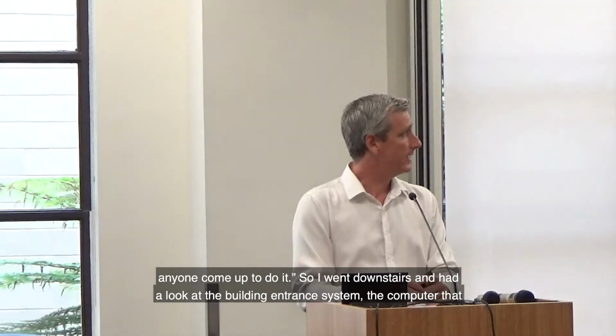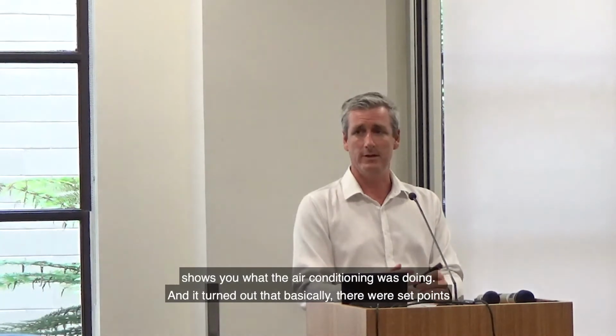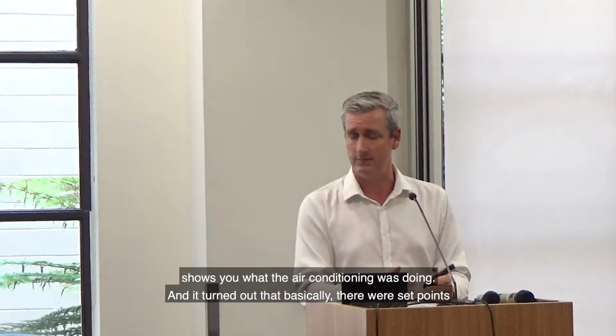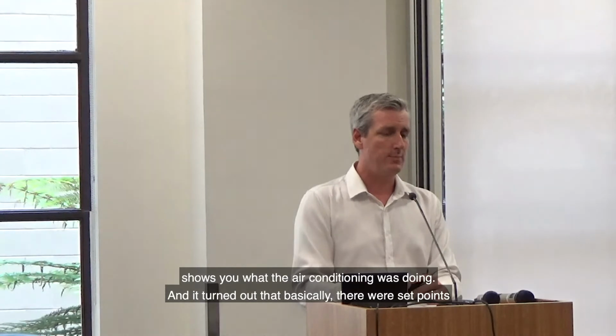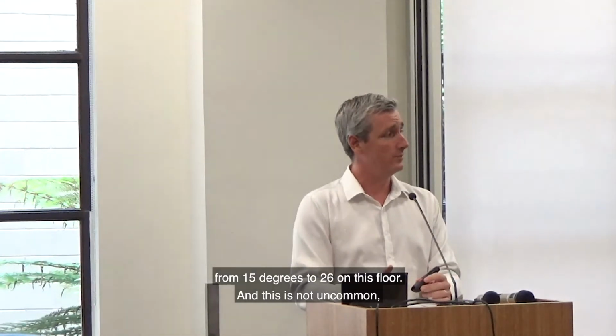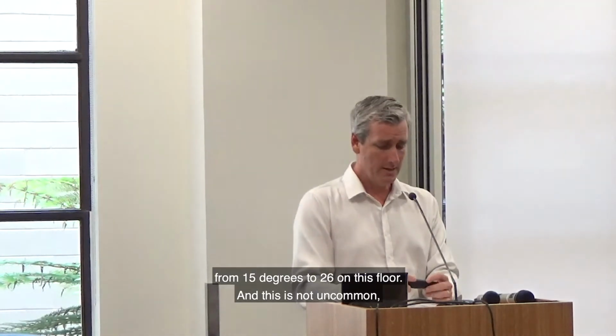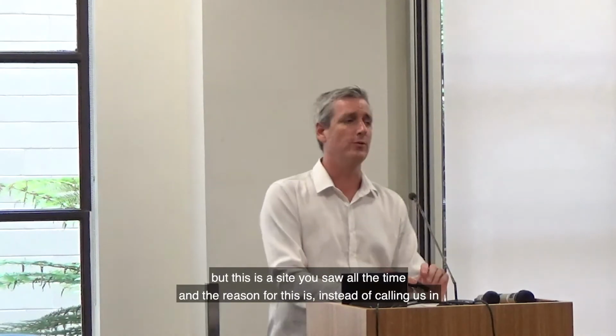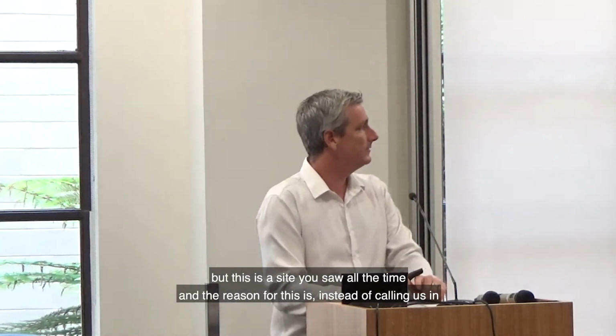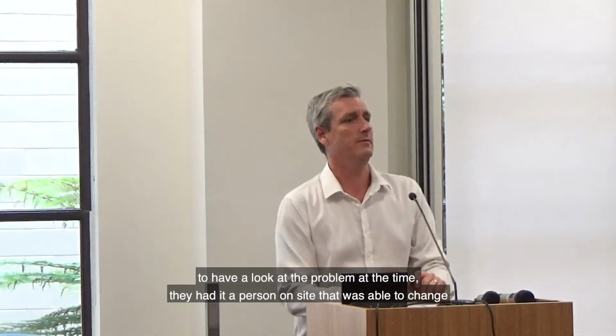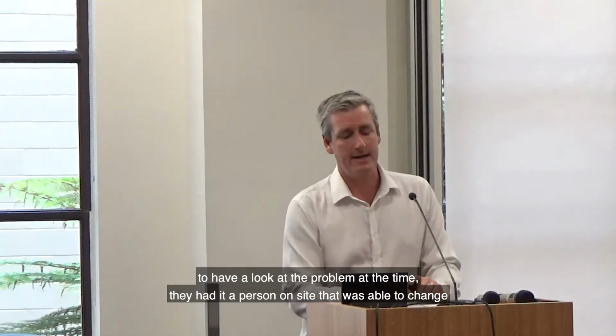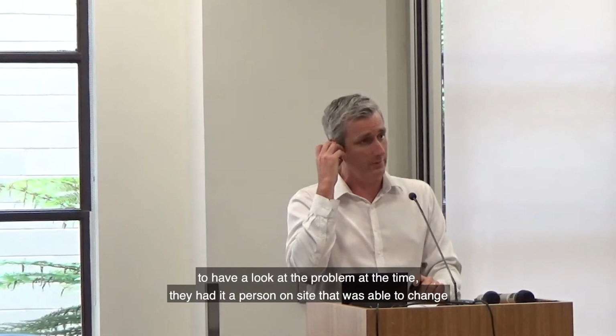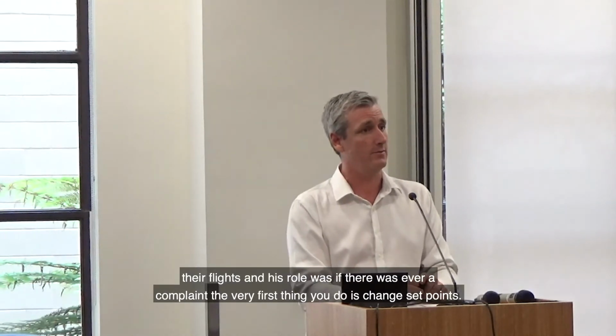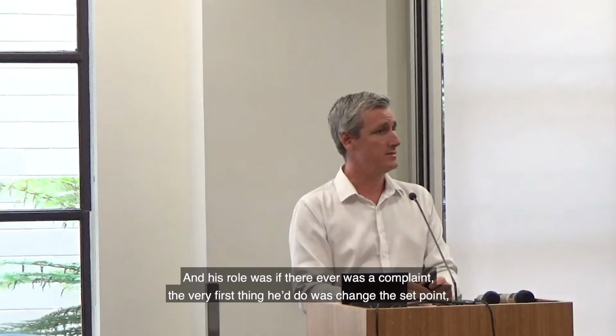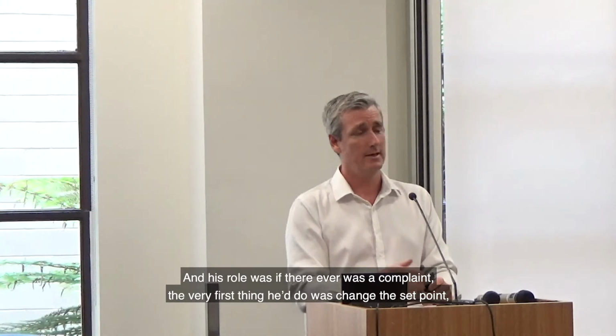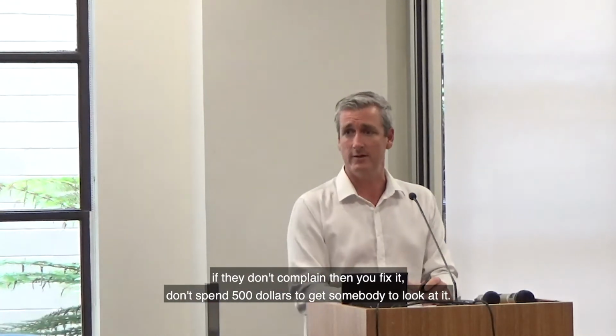So I went downstairs and had a look at the building management system, the computer that shows you what the air conditioning on that floor is doing. It turned out there were set points ranging from 15 degrees to 26 degrees on this floor. This isn't uncommon, you see it all the time. The reason is, instead of calling us in to look at the problem, they had a person on site who could change set points. His role was: if there was ever a complaint, the very first thing you do is change the set point. If they don't complain, then you fix it. Don't spend $500 to get somebody to look at it.